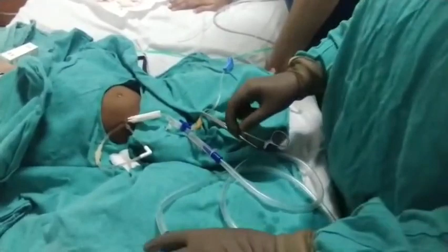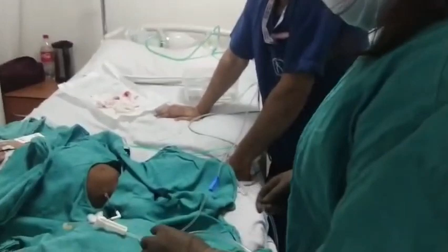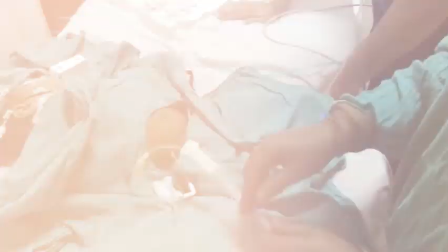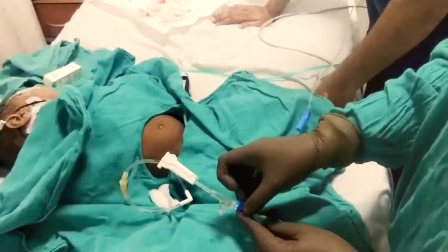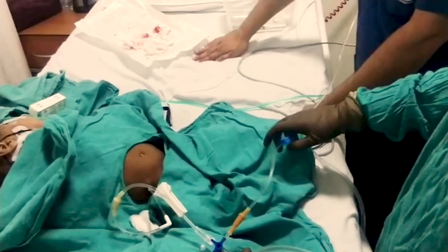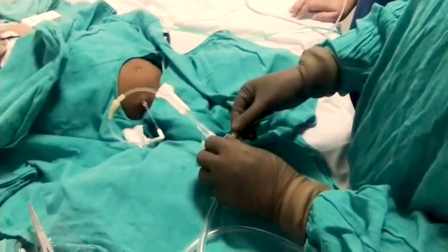So now you have already filled in the peritoneal cavity. Whatever fluid you have filled in will start coming out. To check the patency of our PD catheter, you can check. You can see, we open from this side. Let fluid go into the PD catheter. If you can see, there is a free flow from here into the PD catheter. Okay, so this is the free flow of PD fluid going inside, and then you make it go outside. You can actually see all the PD fluid starts coming out.